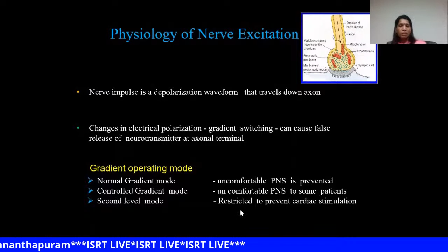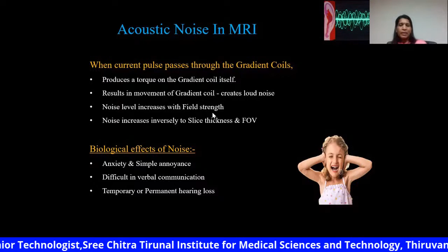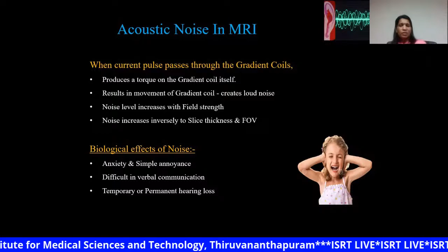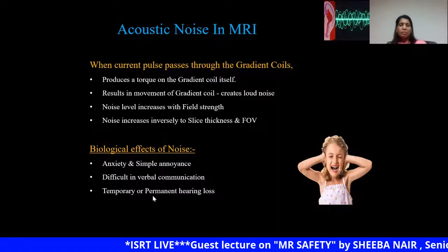When the gradients are switched at a rapid rate, there will be movement of the gradient coils. There will be torque exerted on the gradient coil, which appears as loud noise. So when the gradient switching is faster or the field strength is higher, the noise will be higher. This noise can produce anxiety in the patient. It will make verbal communication difficult, and it can also produce temporary or permanent hearing loss.